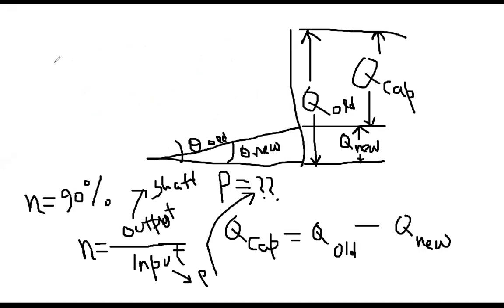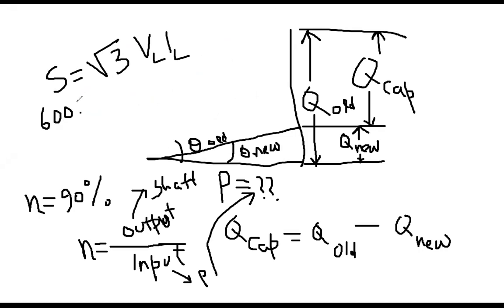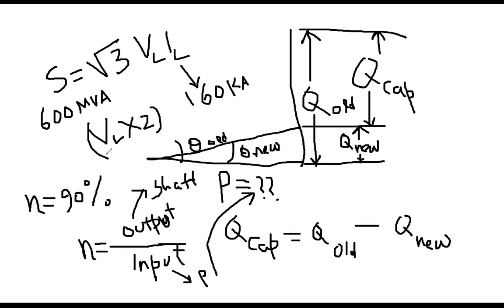Sindhuja, for the next part, you need to use this equation, S equal to √3 VL IL, where S is your MVA. S was 600 MVA, and IL was given as 160 kiloampere. So from there you get the VL value, and that is the terminal voltage of the generator. Then there is the transformer, so you have to multiply that value by 2. That will be your answer. So that should be 4.33 kV.